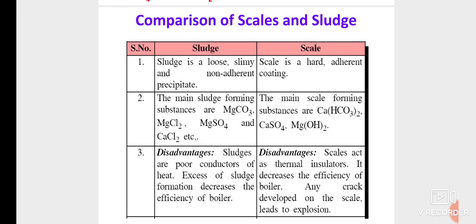Comparing scale and sludge: sludge is a loose, slimy, non-adherent precipitate on the inner walls of the boiler — remember 'S' for sludge means soft/loose, slimy, non-adherent. Scale is a hard, adherent coating inside the boiler. Examples of sludge: magnesium carbonate, magnesium chloride, magnesium sulfate, calcium chloride. Examples of scale: calcium bicarbonate, calcium sulfate, magnesium hydroxide. For examination purposes, write at least two examples of each — sludge and scale.